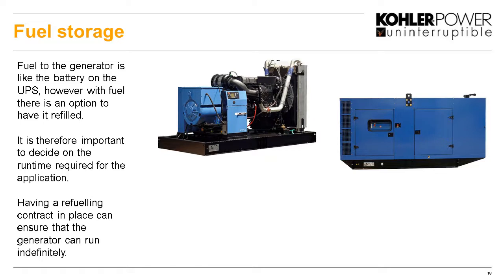So coming back onto fuel storage. Now, fuel to the generator is like a battery to the UPS. However, a battery is very difficult to refill on the go. But with a generator, we have the option that it can be refilled while it's running. And this is very important to consider. So we can decide how much runtime we need for the generator. Now that can be from hours to days to weeks, and then we can decide how much fuel we actually need to have on site, because if we can refuel it and get fuel in the required time, we can limit the amount of fuel that we have to actually store on site.